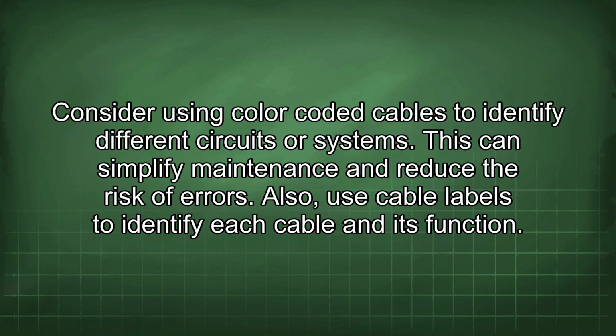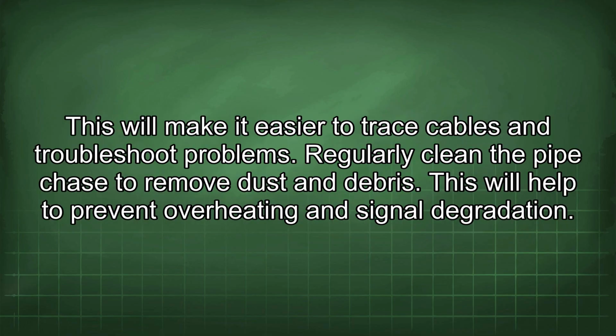Consider using color-coded cables to identify different circuits or systems. This can simplify maintenance and reduce the risk of errors. Also, use cable labels to identify each cable and its function. This will make it easier to trace cables and troubleshoot problems. Regularly clean the pipe chase to remove dust and debris. This will help to prevent overheating and signal degradation.